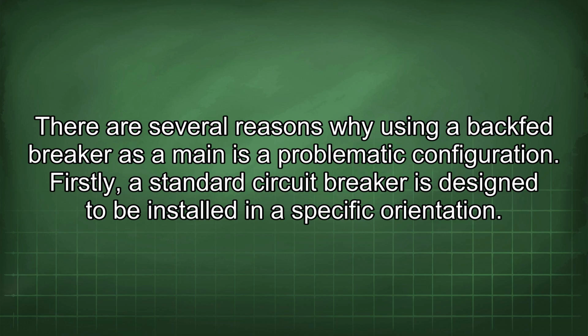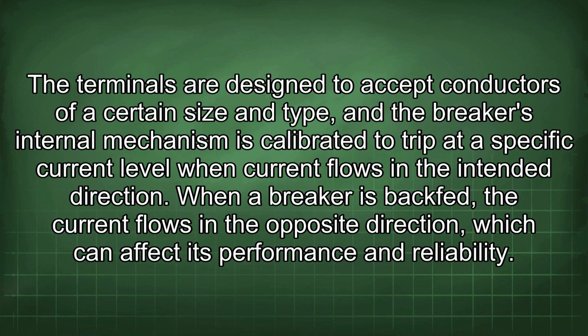Firstly, a standard circuit breaker is designed to be installed in a specific orientation. The terminals are designed to accept conductors of a certain size and type, and the breaker's internal mechanism is calibrated to trip at a specific current level when current flows in the intended direction. When a breaker is backfed, the current flows in the opposite direction, which can affect its performance and reliability.